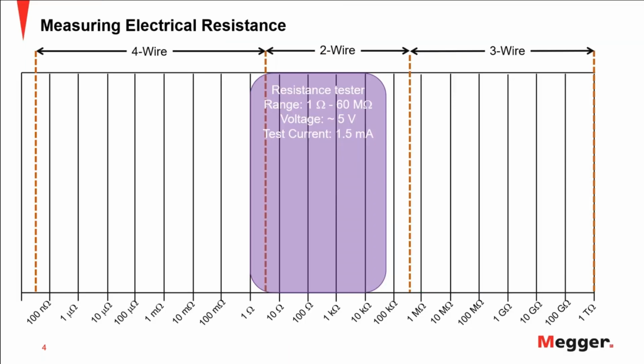Then another section in this range is the typical digital multimeters. And these digital multimeters can measure resistance, absolutely, definitely they can measure. However, you can see the range of measurement is very limited, from 1 to 60 mega ohms. It uses very low voltage, 5 volts, and very low current to do this measurement.